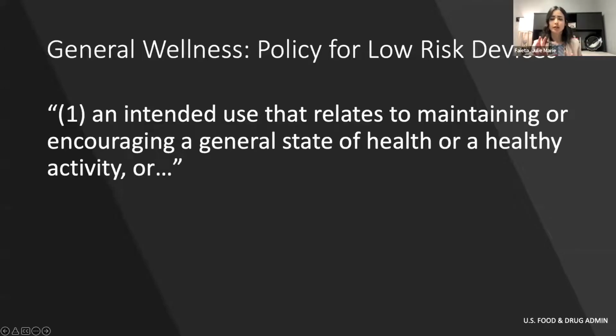In order to gain a better understanding of what a CMD is, let's talk about what a CMD isn't. The FDA's general wellness policy for low-risk devices describes software items that are considered low risk. It categorizes them under two descriptors or definitions, the first of which would not be considered to describe a medical device. This first definition describes software as having, quote, an intended use that relates to maintaining or encouraging a general state of health or healthy activity. So that's not really a medical device.